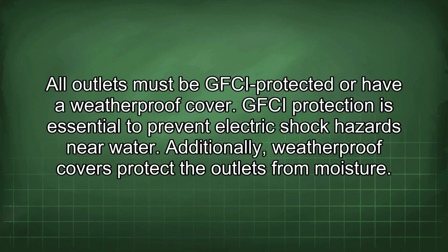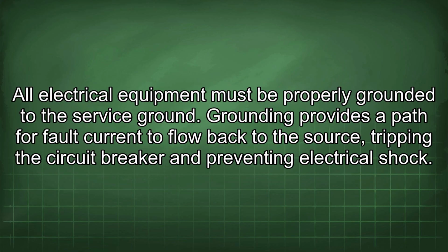All outlets must be GFCI protected or have a weatherproof cover. GFCI protection is essential to prevent electric shock hazards near water. Additionally, weatherproof covers protect the outlets from moisture. All electrical equipment must be properly grounded to the service ground.